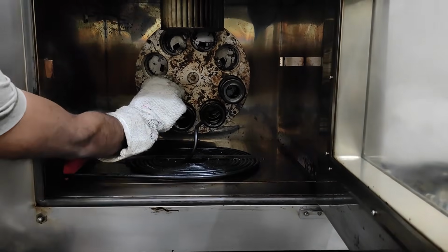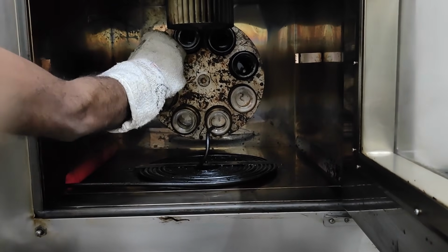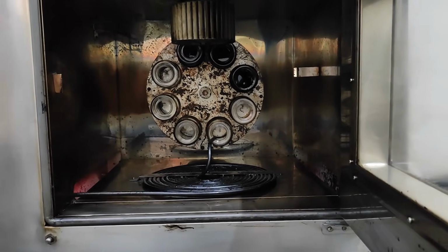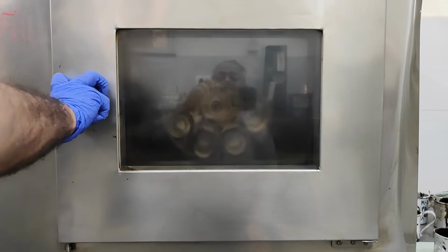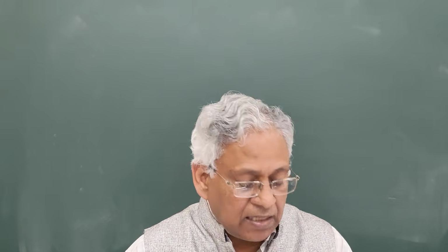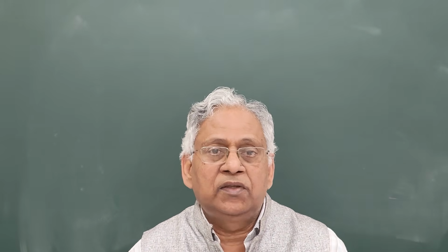After you put all the containers in the holes, you close the door and rotate the carriage assembly at 15 RPM, and maintain the sample in the oven with the air flowing and the carriage rotating for the conditioning time duration. This conditioning time duration is 85 minutes to 92 minutes depending upon the elevation of the laboratory.